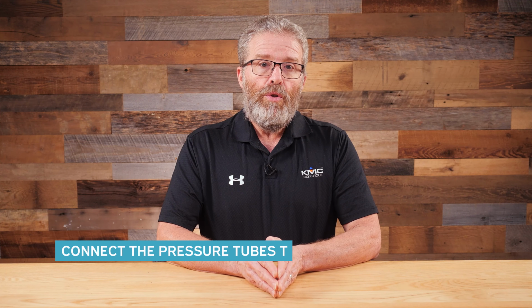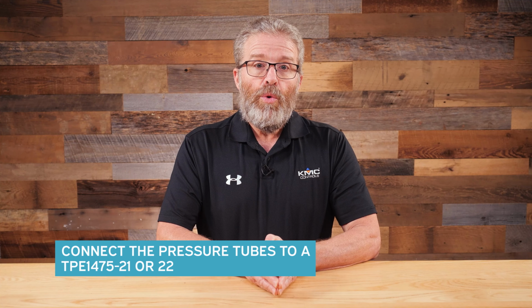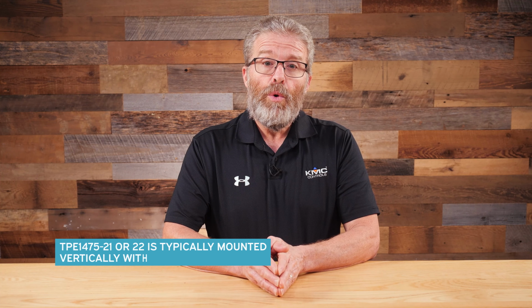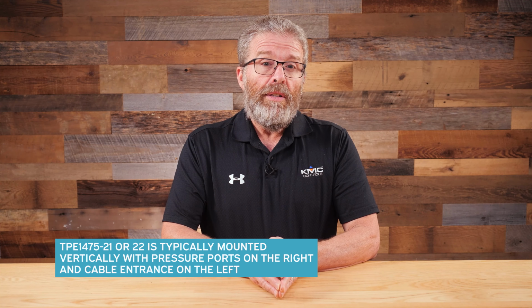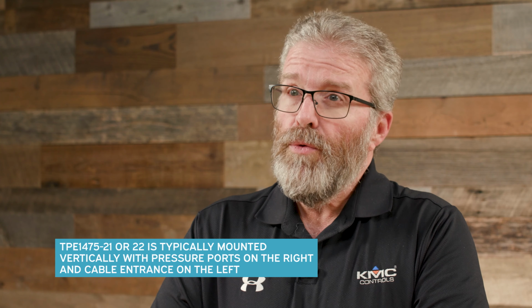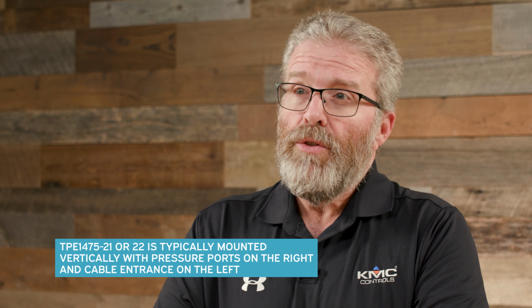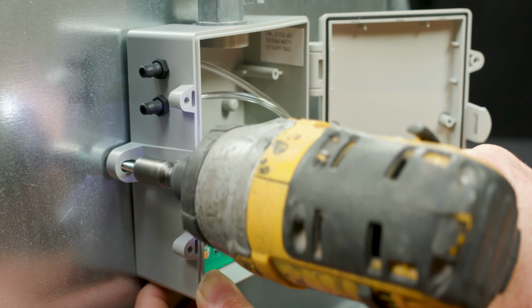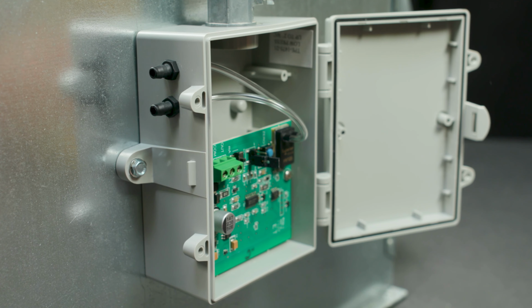If you are using a BAC 5901C AFMS, you will need to connect the pitot tubes to a TPE 1475-21 or -22. When installing the transducer, ensure there is enough space around it to make the tubing and electrical connections. Note, the TPE 1475-21 or -22 may be mounted in any position, but typically is installed in a vertical surface with the pressure ports on the right and the cable entrance on the left. Avoid locations with severe vibrations or excessive moisture. The enclosure has a standard 1/2 inch conduit opening and may be installed with either the conduit coupler or a gland type fitting. Use screws threaded through the case's mounting holes to fasten the assembly to a location near the array of pressure flow pickup tubes.